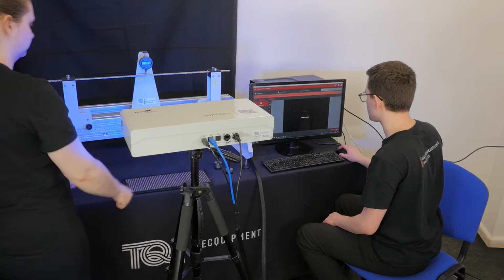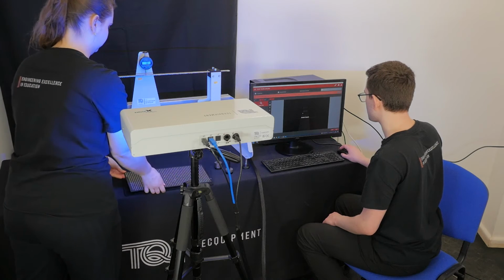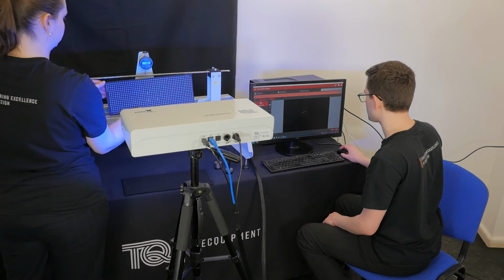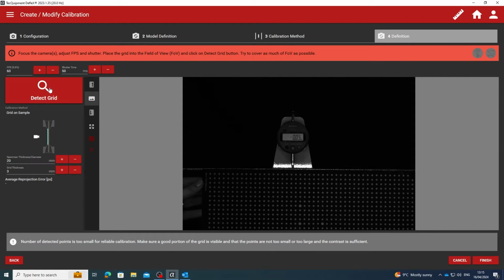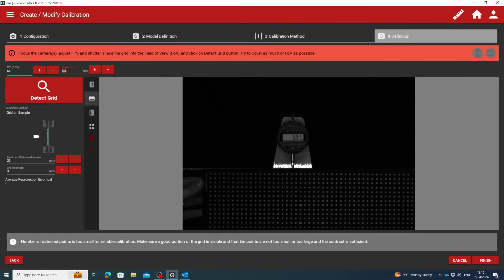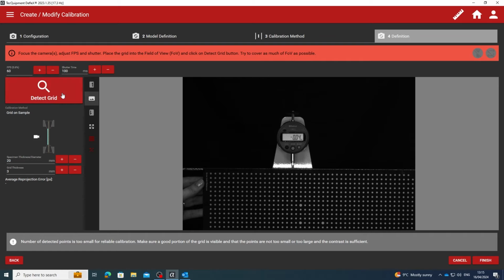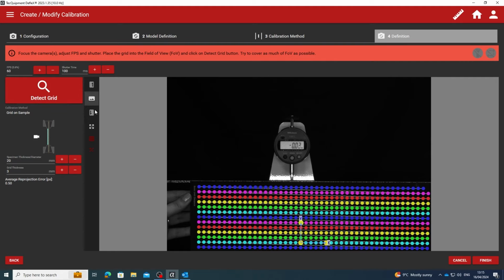Place the grid flush with the specimen in front of the camera, covering as much of the field of view as possible. Set the specimen thickness and the grid thickness, and then press Detect Grid. The grid should be detected by the system, and the colorization of the grid indicates that it's been detected correctly. Click Finish to complete the calibration.